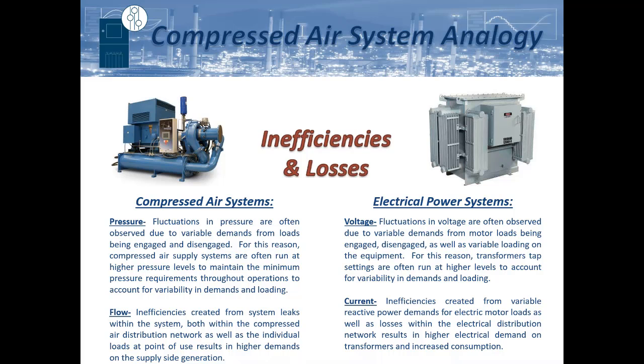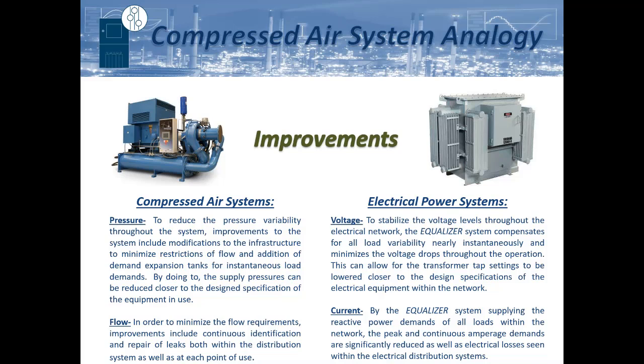And similarly, as we just saw there, the same holds true with voltage. When you have a large inrush of current demand, all of a sudden that can have a significant impact on the voltage levels. And with a compressed air system, you also have inefficiencies in flow, whether from system leaks or from turbulence, which has a good correlation with the reactive power demands as well as the harmonics in the system. It's just resistance to the flow. So what we can do to improve upon that in a compressed air system, if you have wide variability in the network pressure, is that a facility might incorporate a demand expansion tank so that it can provide that instantaneous pressure and compensate for those large loads being brought in.